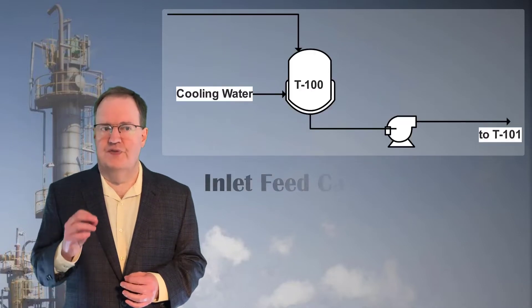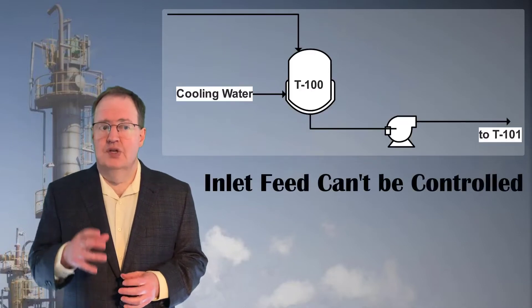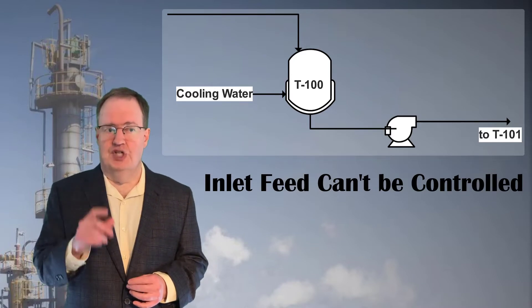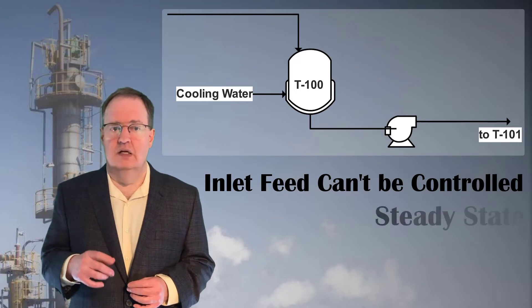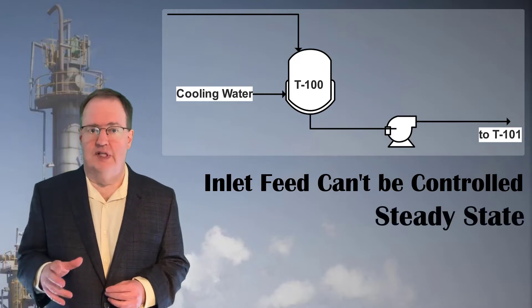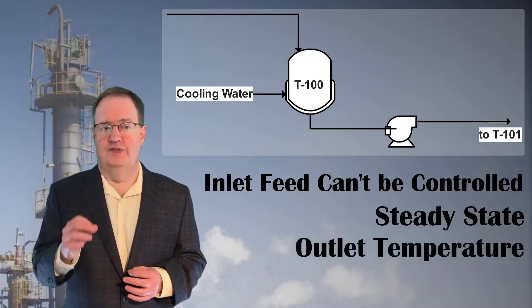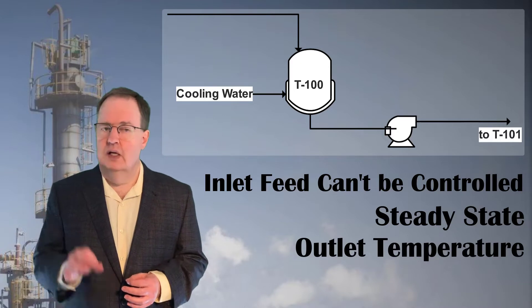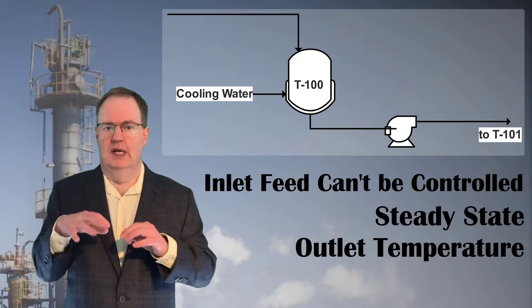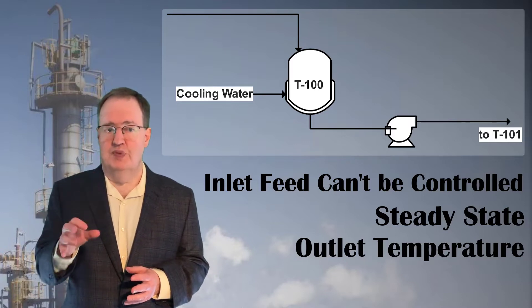Let's look at an example. T100 is the bottoms receiver of a distillation column. It is fed at a variable rate that we can't control, so this unit needs to react to that changing flow. The objectives for this unit are to maintain steady state by holding a 50% level in T100, and to cool the fluid so that the feed to T101 is at 50 degrees C. Pause the video here and try to write a design for this solution yourself. Note that the pump is single speed, so flow control should be accomplished with control valves.